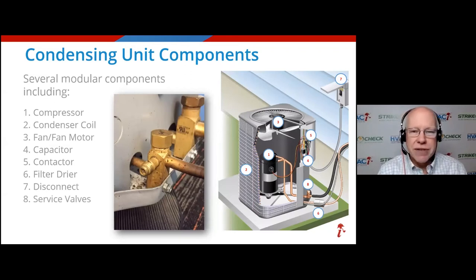We also have the service valves. Again, they don't show up on too many claims, but they're down at the bottom. They're usually facing towards this structure and they really have two functions. One is the technician can put their gauges on it, run the system, check the high and low pressures and use that to diagnose what might be going on with this system. The other thing they do is you can add or remove refrigerant from the service valves, and that's called charging or evacuating. Charging is adding refrigerant, evacuating is taking refrigerant out, and that's probably what it's called in your estimating software as well. So charging and evacuating.